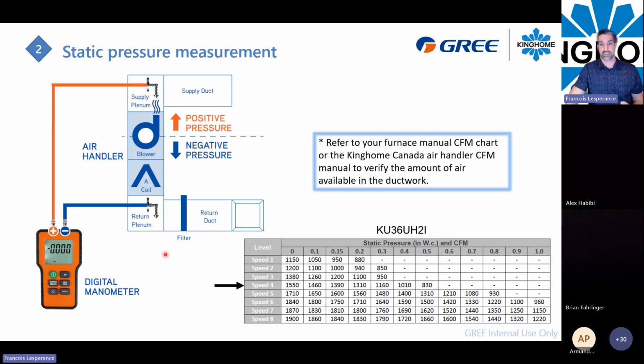All those measurements are, first of all, to reduce the pressure in the ductwork, so reduce the noise, but also have the right amount of air going through that A-coil and provide the right rise of temperature in the ductwork by using the heat pump. Okay, and another thing, what is the ideal static pressure we recommend for our units? Well, there is no ideal static pressure. It's all regarding how the ductwork is built.